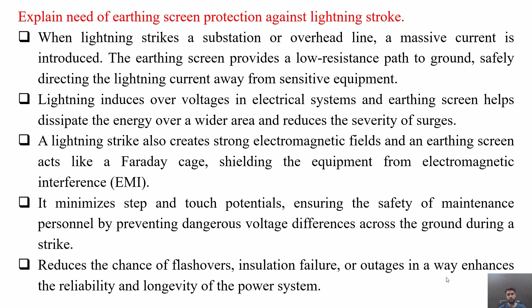It provides a low resistance path to ground, safely dissipating lightning currents. It helps to minimize high voltage transients induced by lightning strikes, protecting insulation and equipment. It acts as a Faraday cage, protecting control and communication circuits from electromagnetic interference. It reduces outages and downtime due to lightning related faults.